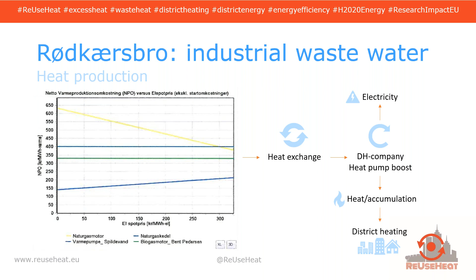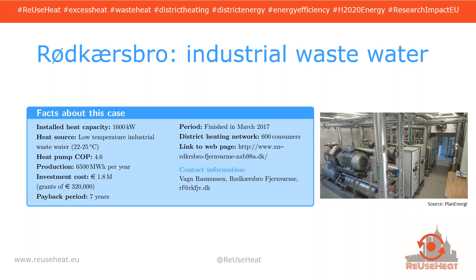To sum up the facts about this case: they installed a heat pump that is relatively small compared to some other Danish cases, at 1.6 megawatts. They exploit low temperature industrial wastewater and obtain a quite high COP of 4.6, with an okay production of 6,500 megawatt hours every year, and a relatively small investment cost of 1.8 million, of which they received grants of about 300,000. So the payback period for the system was 7 years.